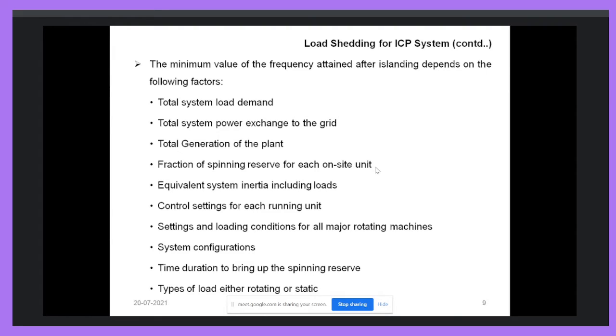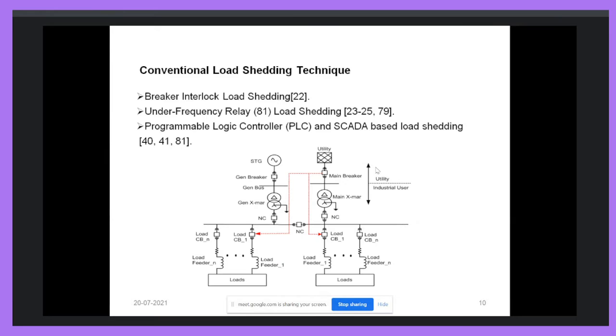Control settings of each running unit, obviously generator settings, also affect the variation of frequency. Then system configuration, the time and duration to bring in the spinning reserve, and the type of load, either rotating or static. All these are the factors which will affect the deviation of frequency after islanding of the industrial system or generating system. Now I am going to discuss the conventional load shedding techniques one by one.